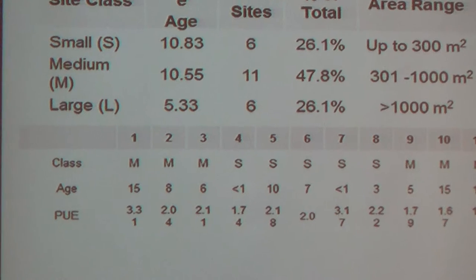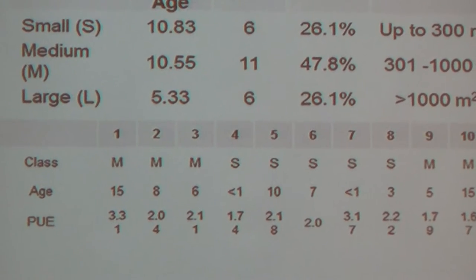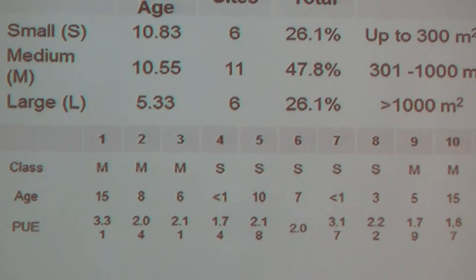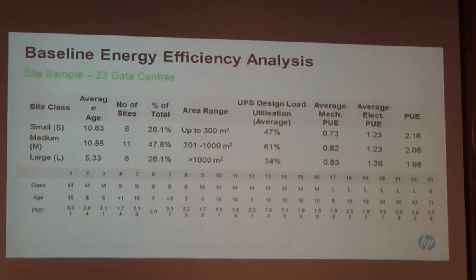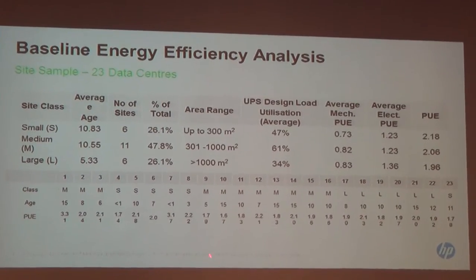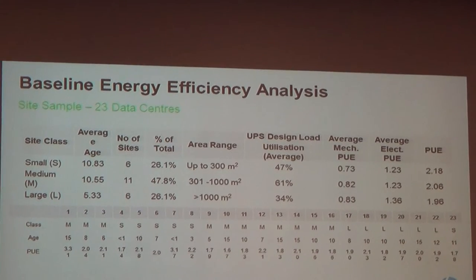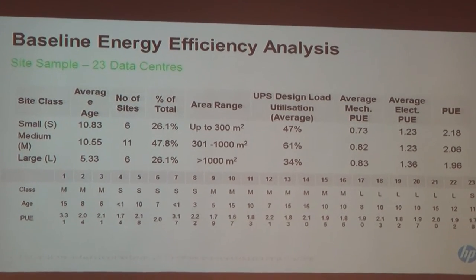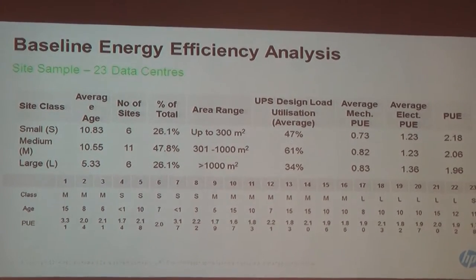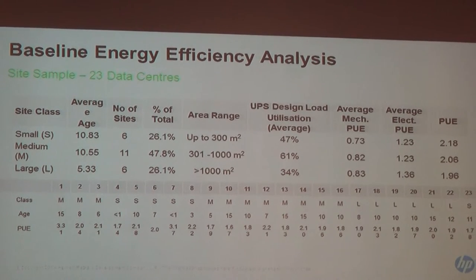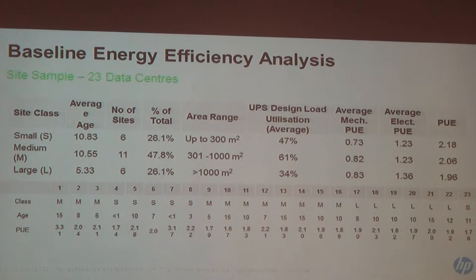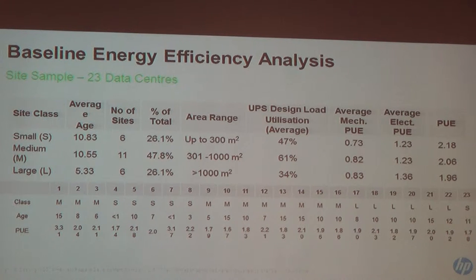Now you might say that's a poor data centre, and in operational terms it probably was at the time. But because it was less than a year old—in fact only 6 months old—this was due to the fact that when you calculate PUE, you're looking at the total IT capability and the total M&E capability. So if you have 2 chillers and switch one off, you can't ignore that in your PUE calculation.